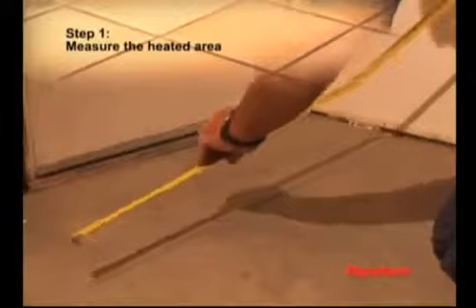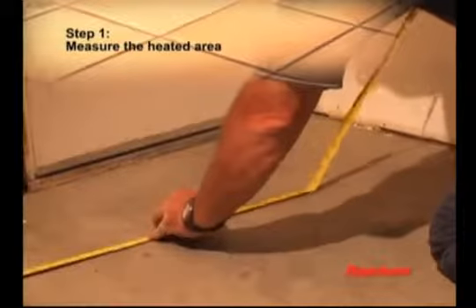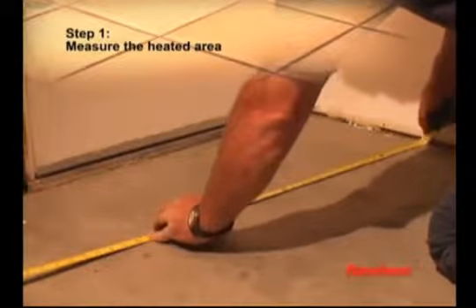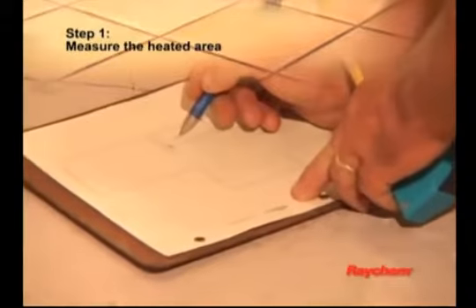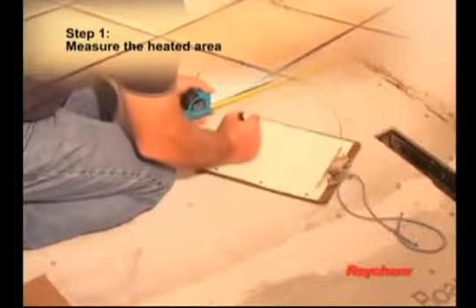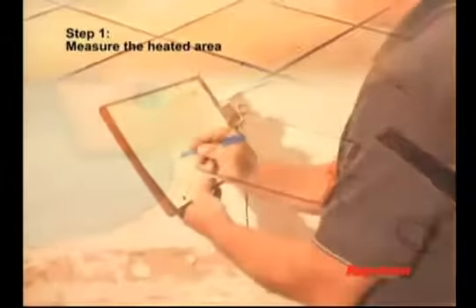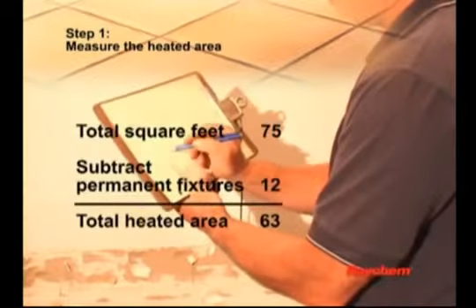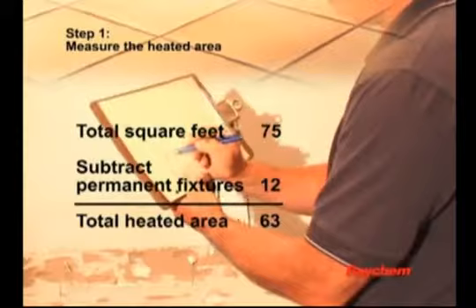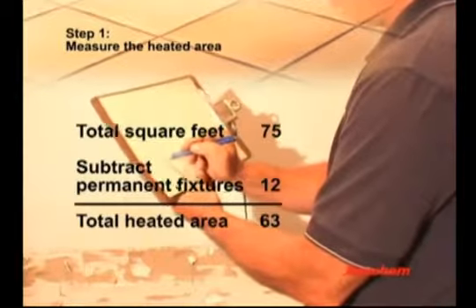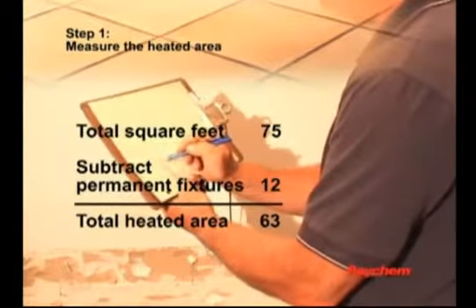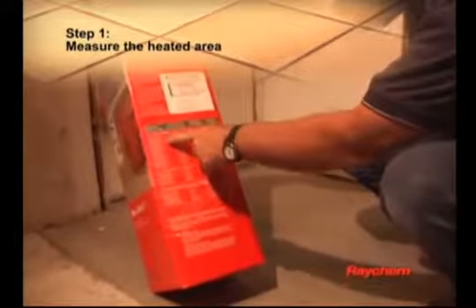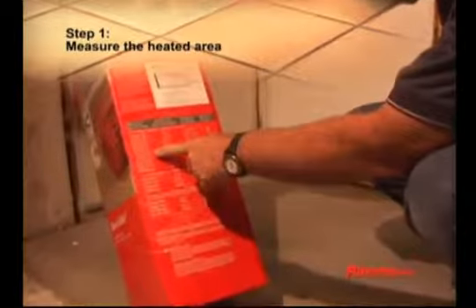QuickNet comes in various sizes, designed to fit the heated area of any floor. To determine what mat size you need, measure the total area of the room and subtract the areas that contain permanent fixtures, as well as any areas you do not want warmed. For example, the total area of this bathroom is 75 square feet. When you subtract the 12 square feet for the vanity, shower, and toilet, the heated area is only 63 square feet.